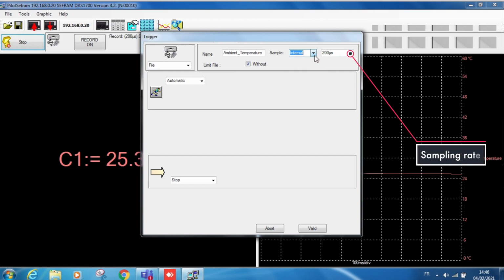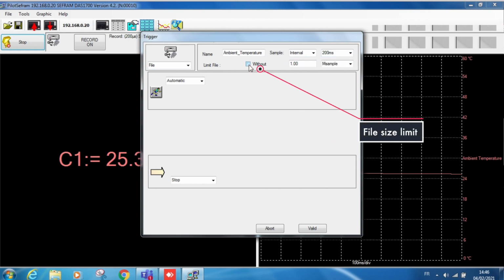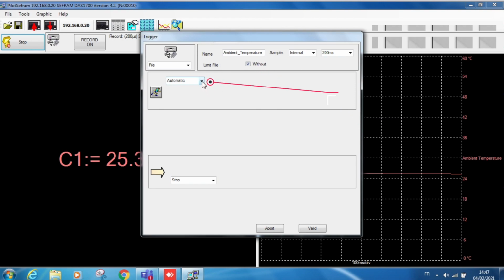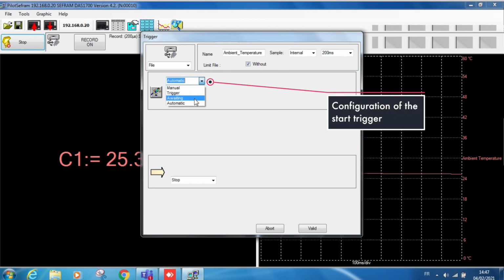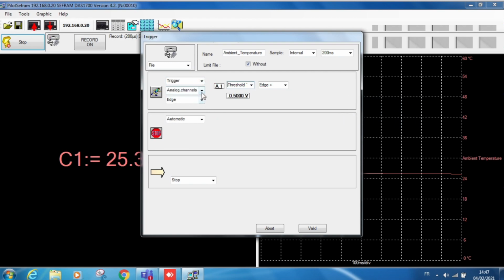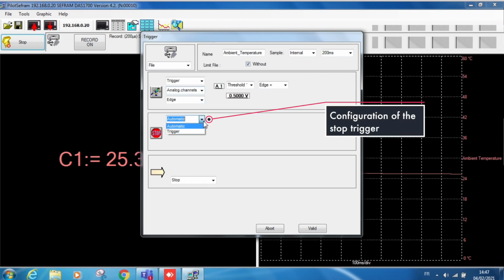We stay on an internal sampling and put a sampling rate of 200 milliseconds. We can limit the length of the file or record the entire internal memory. We do not set a file limit. We can choose between a manual, awaiting, or automatic trigger. If we choose trigger, there are different types: analog channel, logic channel, or combination analog channel. In our case, we choose an automatic trigger for both start and stop.